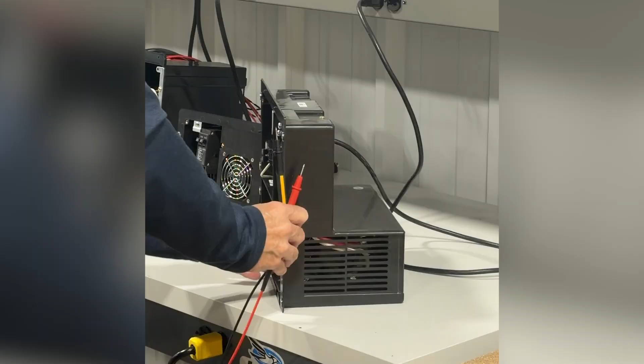These power converters are auto detect, so they will detect what type of battery you've got, whether it's a lead acid battery or a lithium battery. The only way these things know what battery is in there is to figure out how deep they discharge and how long it takes to charge, and that takes multiple charge and discharge cycles for both of these auto-detect converters to figure out what kind of battery it is.